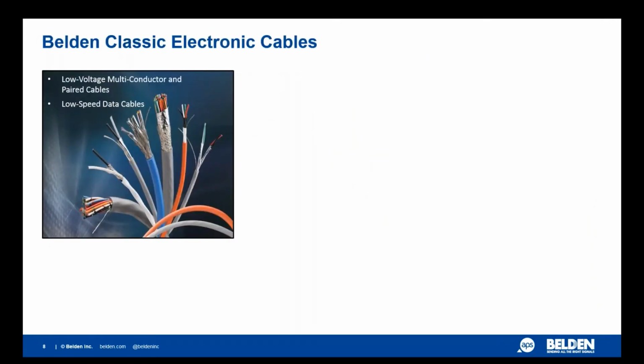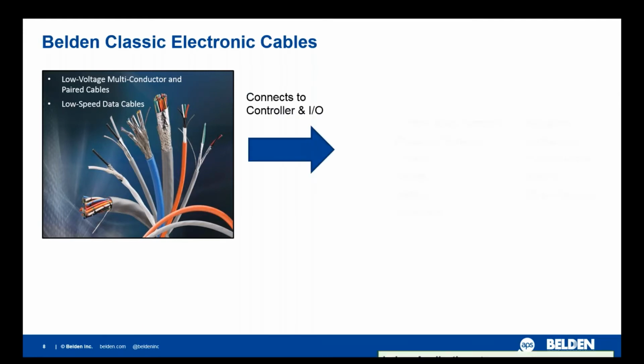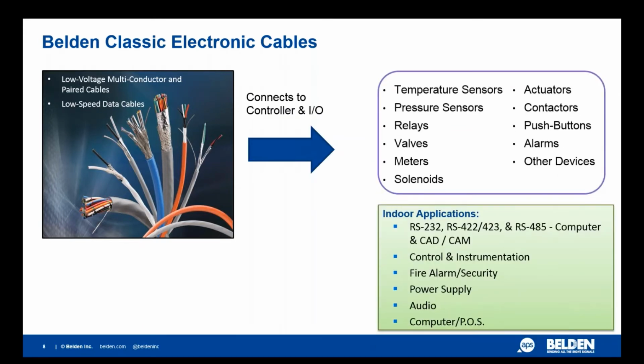Classic cables are low voltage multi-conductor and paired cables, also used for low speed data signals. They connect to a controller and an I/O. In the industrial market, the cable would connect to a temperature sensor, relay, contactors, push buttons, etc. For indoor applications, it's more to do with RS protocols for computer serial devices, then control and instrumentation, fire alarm/security, power supply, audio, and computer or POS systems.